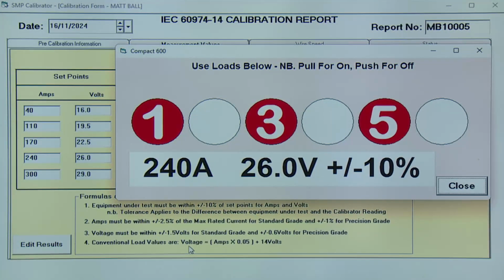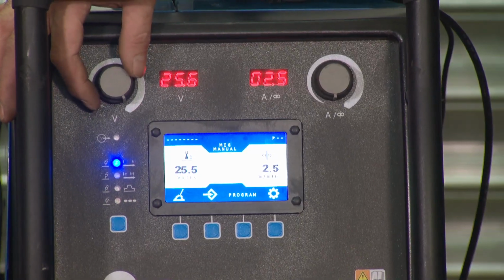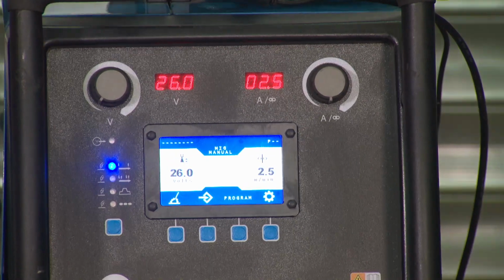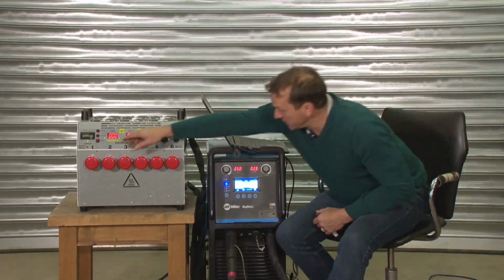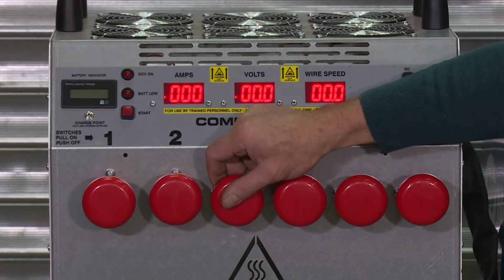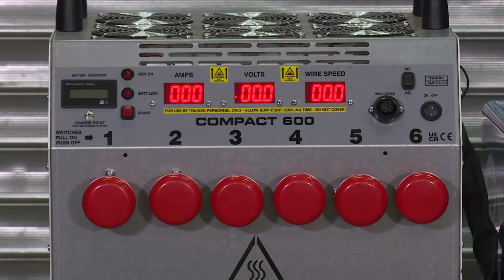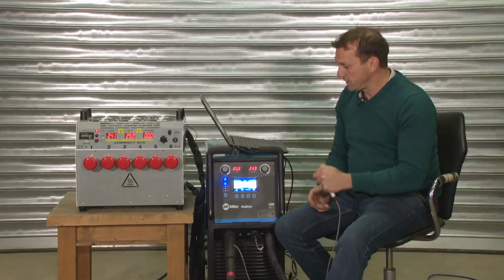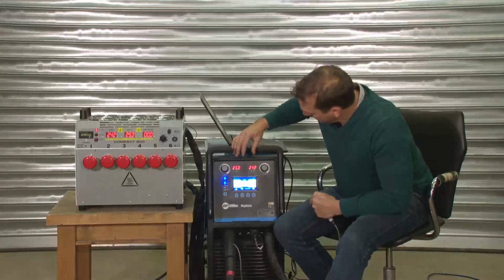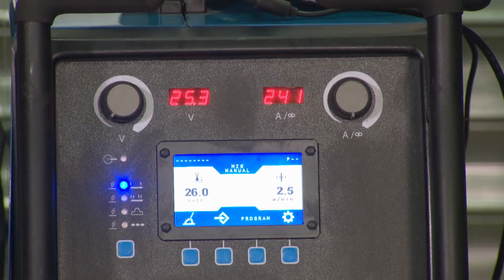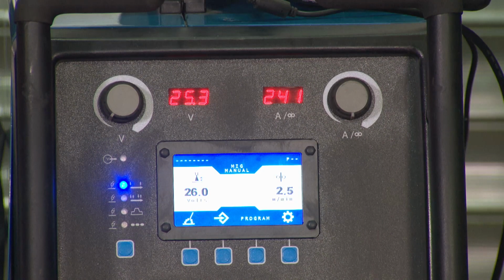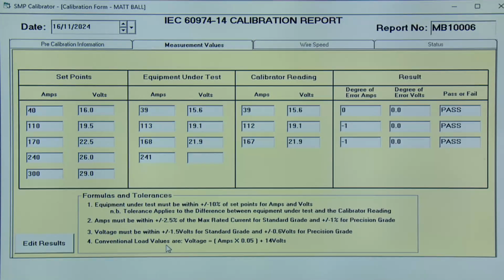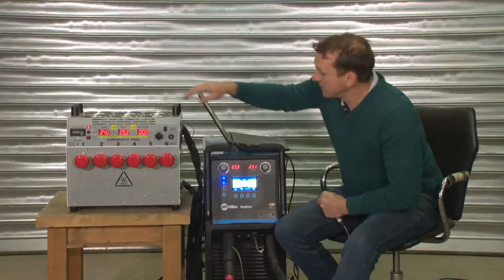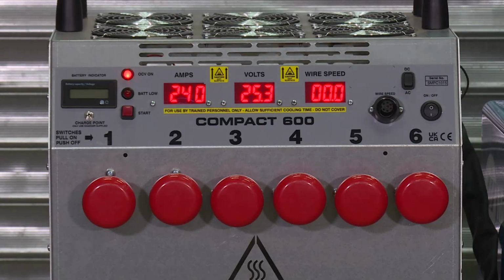And then on to our next reading of 240 amps at 26 volts. So we set the welder to 26 volts. And set the Compact 600 to loads 1, 3 and 5. We energize and take the welder reading. We have 241 amps, 25.3 volts. And then the calibrator reading. We got 240 amps, 25.3 volts.